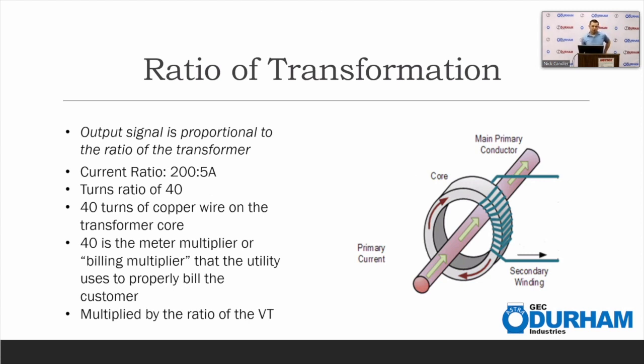So 40 is going to be your meter multiplier, as some call it. Some refer to it as the billing multiplier. But that's the number that the utility uses to make sure that you get charged the right amount. If they were not to use that, then there would be some lost revenue there for sure. So anyway, if you use any voltage transformers, you need to multiply your billing multiplier from the CTs by that ratio as well to get your overall billing multiplier.